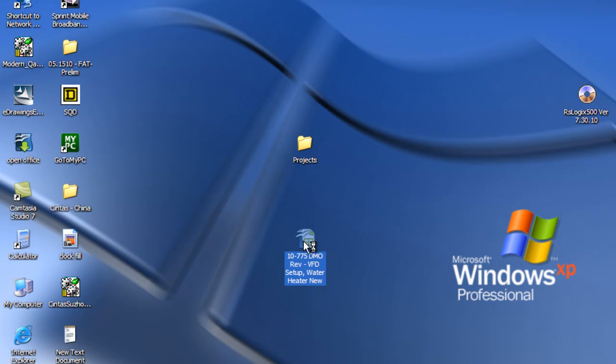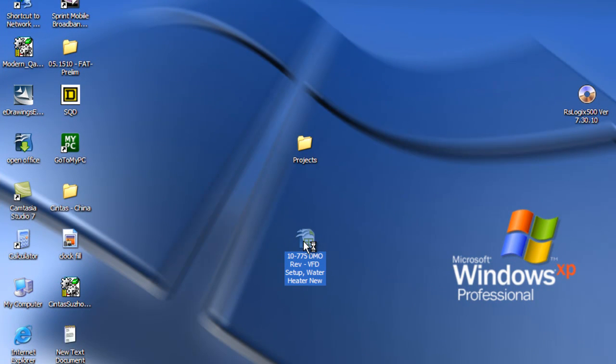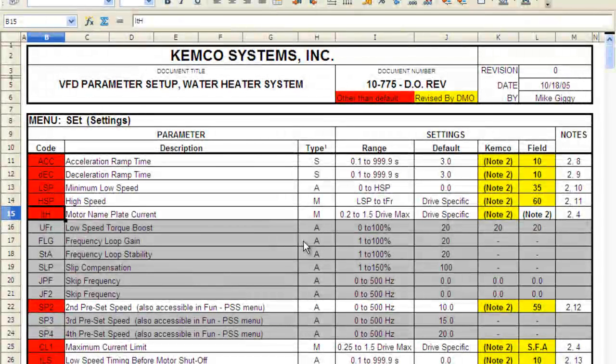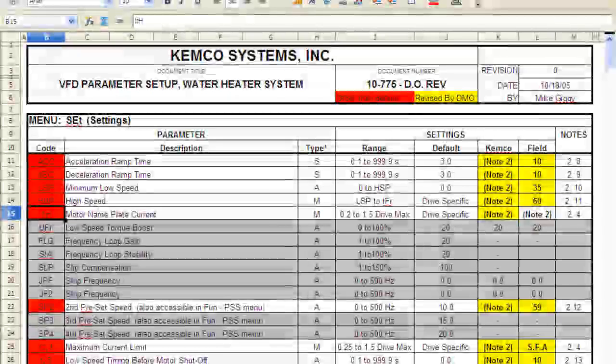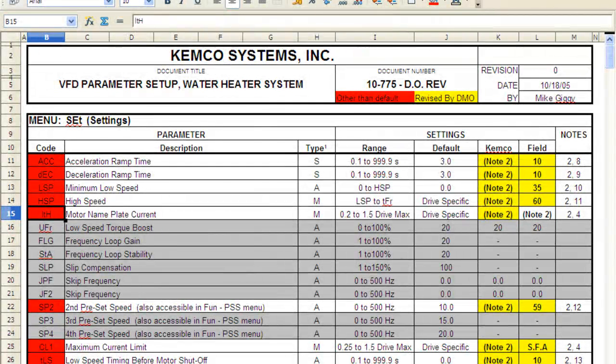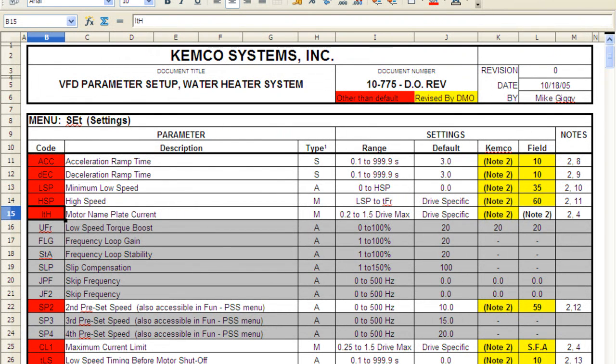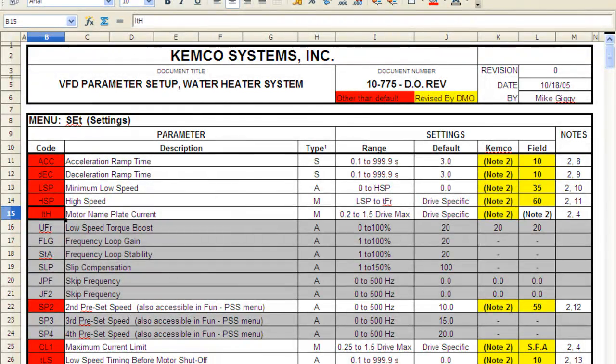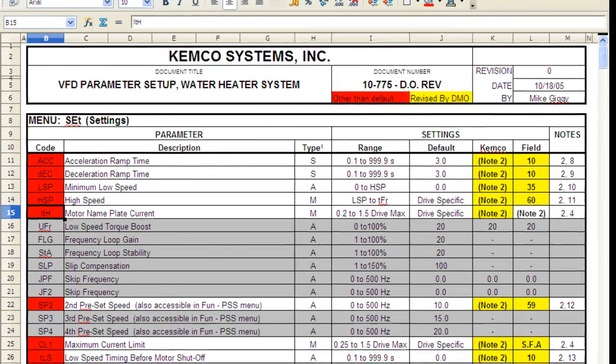It opens up in Excel or free shareware like OpenOffice, which is what it's doing right now. We're going to get familiar with what we're trying to do here and which parameters are important if you ever had to replace your drive, which are indicated in red. But most importantly, when you change a pressure transducer, sometimes it differs from the other one a bit, and we have to change a few parameters.